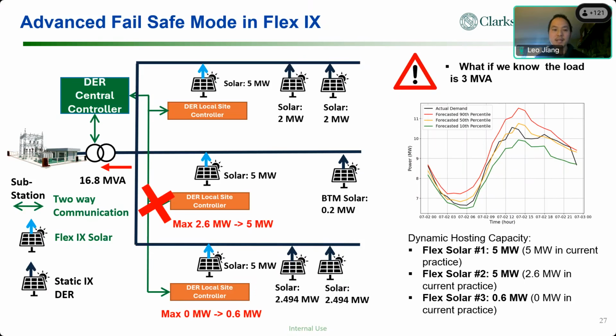Because, as Zach said, for this site the static hosting capacity is indeed 7.6 megawatt. And then we follow the last in, first out (LIFO) curtailment scheme. The first solar farm, the flex solar at the top, has 5 megawatt of static hosting capacity allocated. That's why, even if there is a communication outage, the first flex solar farm will not face any curtailment, because it has 5 megawatt of static hosting capacity allocated.